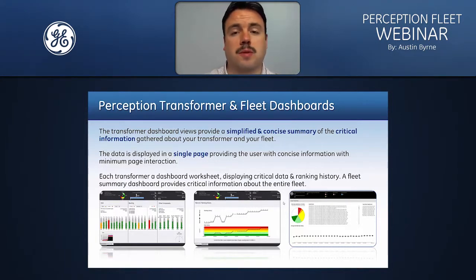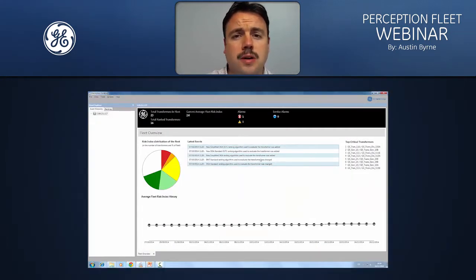So I'm just going to bring up the Perception application to show you how it looks. Here you can see the fleet overview dashboard. At the top, the information in the header shows the total number of transformers in the fleet, how many of those transformers are currently being evaluated, so 16 for this example, the current average fleet risk index, which is 2.6, any alarms that are raised within the fleet, and any of the online devices that are currently experiencing a service alarm.